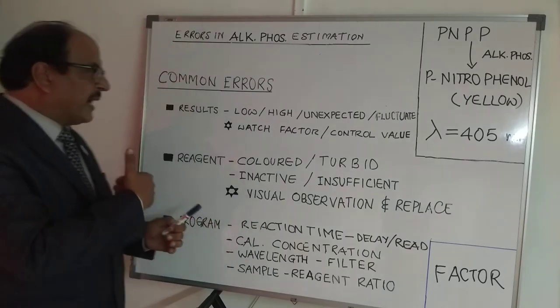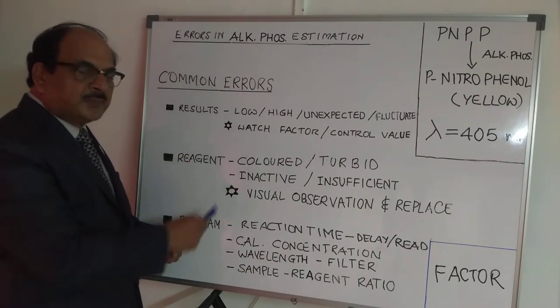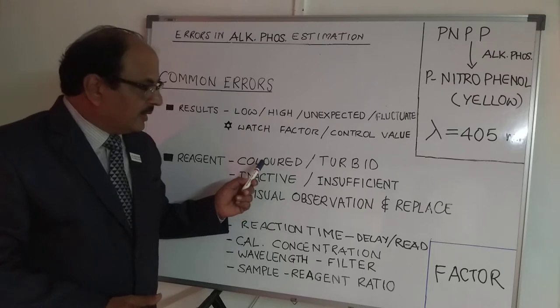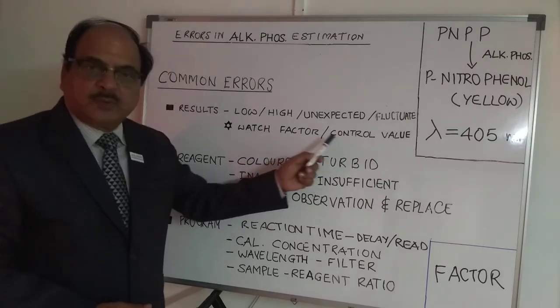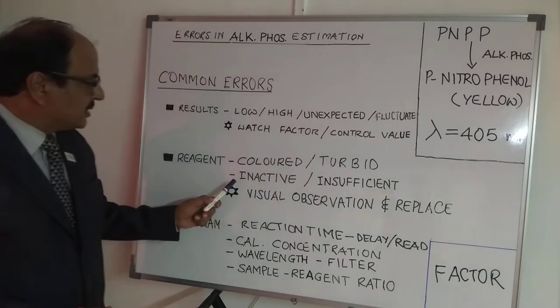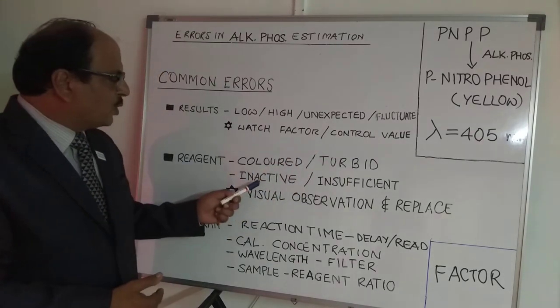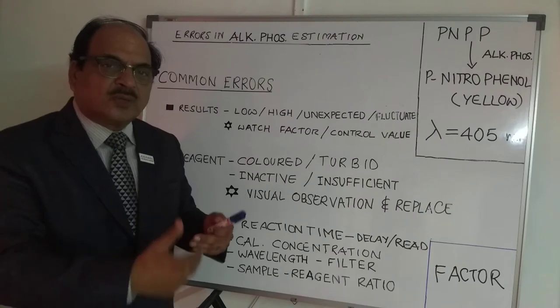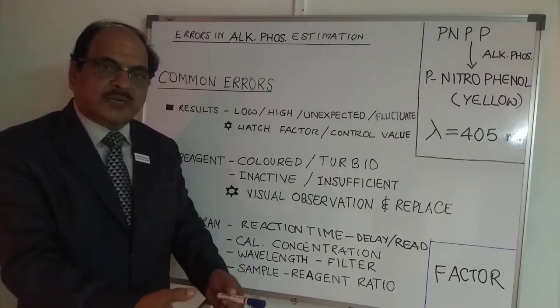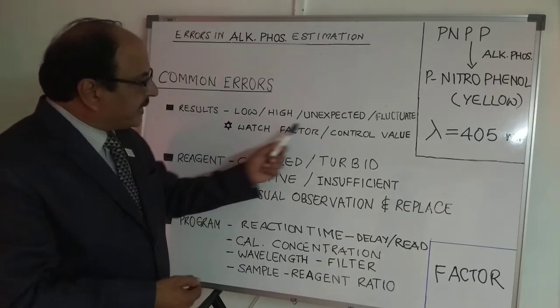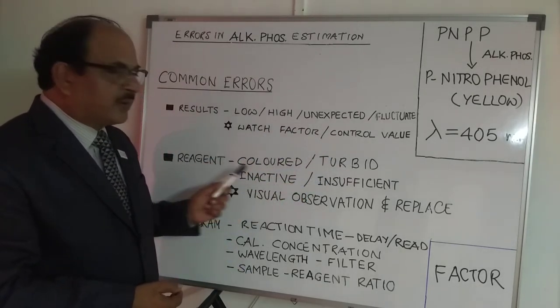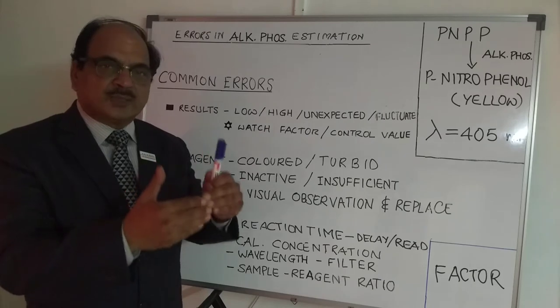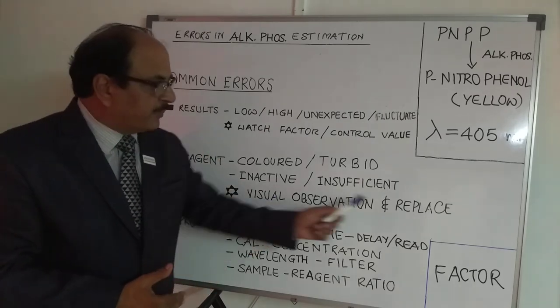The second category is reagent-related errors. These include the reagent becoming a colored compound, a turbid liquid, the reagent being so thoroughly contaminated that it is no longer working (inactive reagent), or the reagent being almost finished such that you are sucking air bubbles along with the liquid while pipetting. To address turbid, colored, insufficient, or inactive reagents, take the reagent out in a clean test tube and inspect it against the light. If you find anything abnormal, just replace the reagent.